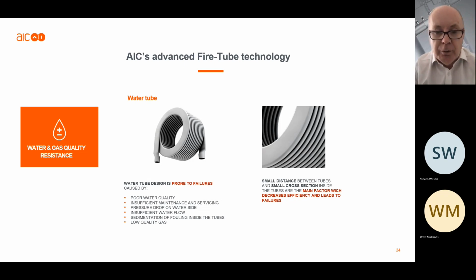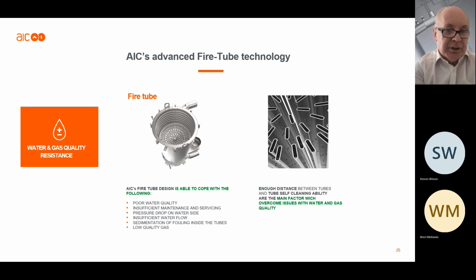Okay, so how does fire tube counteract that? Well, if you look at the heat exchanger here, the first thing is gravity plays a big role in it. It's a down-firing burner, it's a vertical heat exchanger. And you can see from the image on the right hand side there, there are larger waterways. So any build-up of contaminants within the water won't really stick to the side of those tubes because it's a larger waterway. If they do, these tubes expand and contract as they heat up and cool down, so they shake off any debris, and that's out through your system.